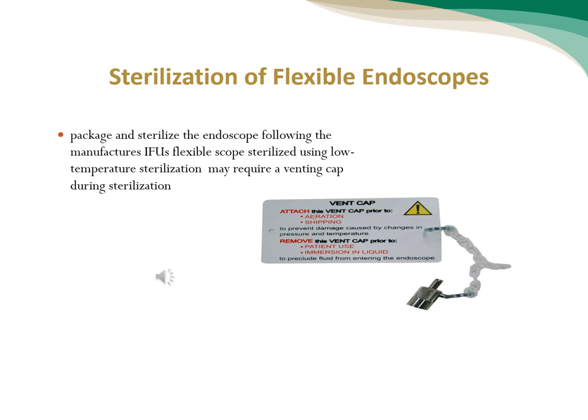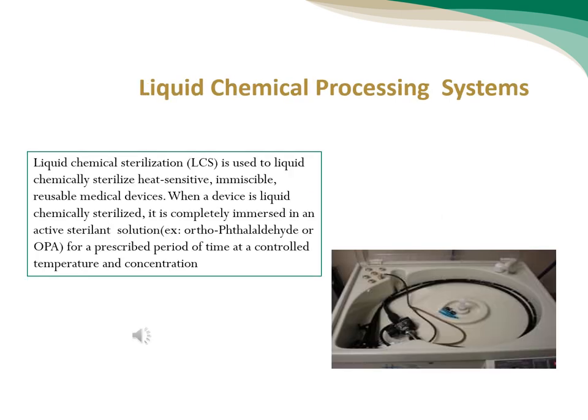Liquid chemical sterilization is used to sterilize heat-sensitive, immersible, reusable medical devices. When a device is liquid chemically sterilized, it is completely immersed in an active sterilant solution — for example, ortho-phthalaldehyde (OPA) — for a prescribed period of time at a controlled temperature and concentration.